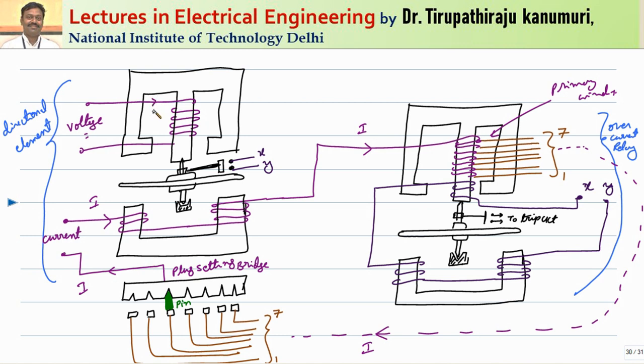The current passes through the plug setting bridge and returns to the supply. The directional relay's upper and lower magnets are always connected to supply, carrying voltage as well as current. A current IV flows due to the applied voltage, and the torque in the disk is produced by the interaction of the flux from IV and the fault current I. When the disk rotates and closes the contacts, this closes the secondary winding of the overcurrent relay, and EMF is induced in the secondary winding by transformer action, producing flux phi 2.